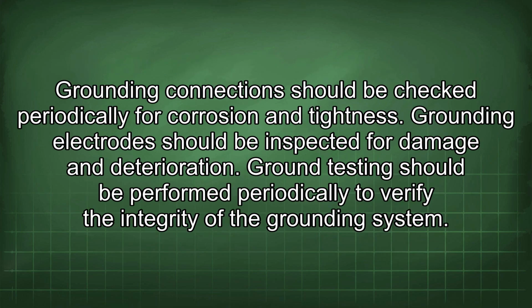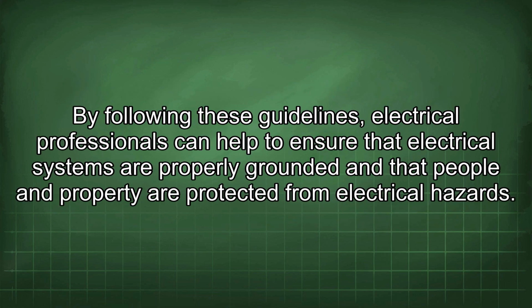Grounding connections should be checked periodically for corrosion and tightness. Grounding electrodes should be inspected for damage and deterioration. Ground testing should be performed periodically to verify the integrity of the grounding system. By following these guidelines, electrical professionals can help to ensure that electrical systems are properly grounded and that people and property are protected from electrical hazards.